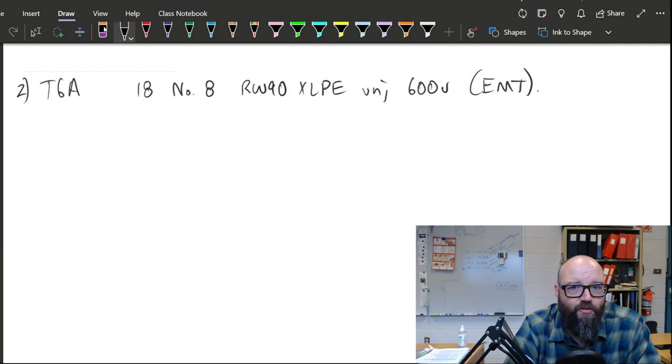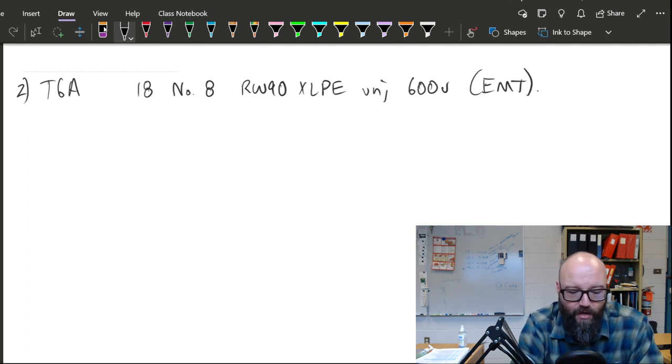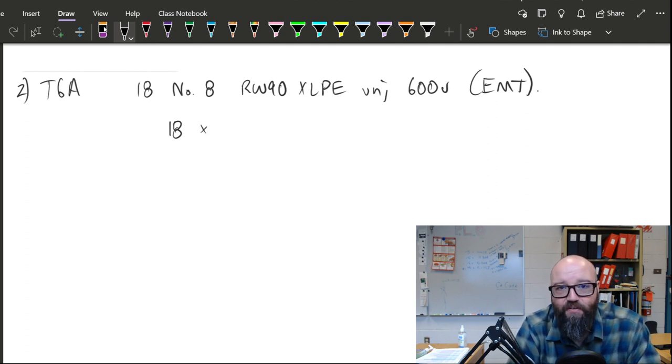But this time, instead of using the multiple occupied area listings, we're just going to use the individual one over on the far left side. So not the diameter, but the first one that gives us the actual occupied area, or the millimeters squared that each conductor takes up. And I can simply do this. I know that if I have 18 conductors, I can multiply that by the individual occupied area of a number 8.